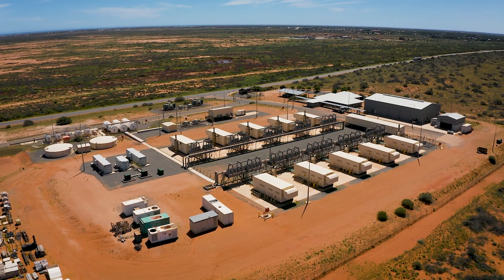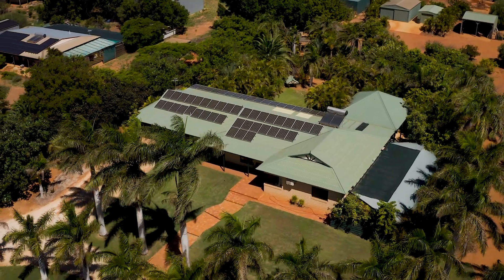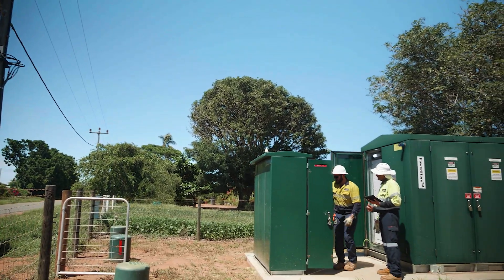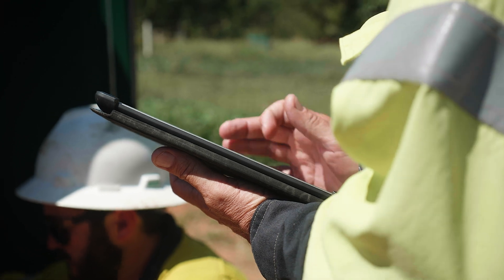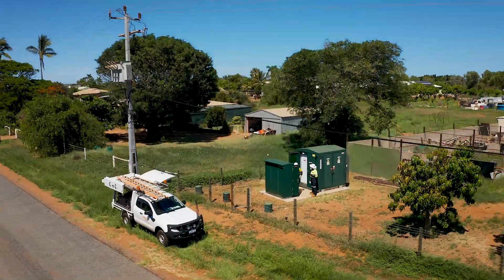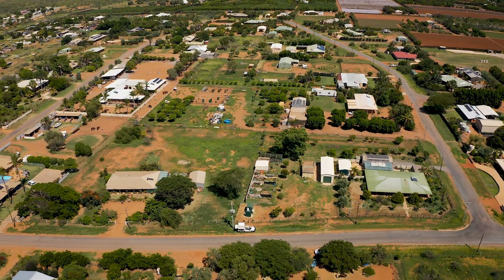With the increased PV on our network, especially in Carnarvon, we're witnessing changes to voltage profiles. The Gibson Street feed is probably one of the most exciting parts of the trial. On this particular network, what we've done is concentrated a lot of the investment in solar and PV to the point where we disconnect that particular part of the network from the rest of the network, so for extended periods of time it will actually operate on its own on purely renewable energy.